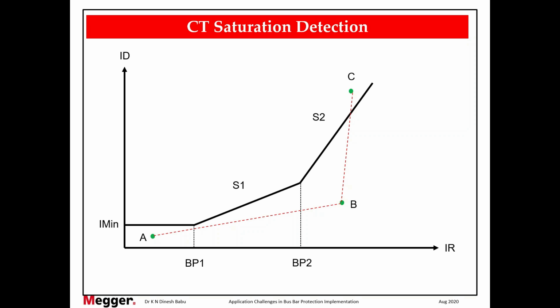Now let us see internal fault CT saturation condition. The fault is internal. I am at point A. Now the healthy current, how will it become fault current? Slowly it will start increasing. Differential current will directly increase and it will move from A to C. So when the locus is A to C, it is internal fault CT saturation. So even though the differential current is at C, if the locus is ABC, relay will not trip. If the locus is AC, relay will trip. That's all. This is how external fault ABC locus, internal fault AC locus. This is how the CT saturation detector works in the relay. This is one universal algorithm which is very famous and available.